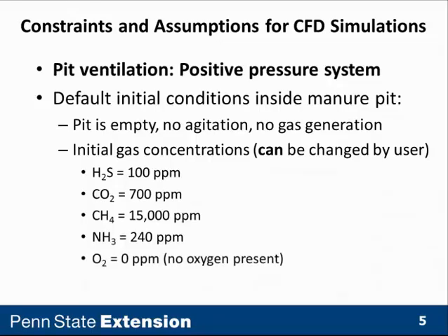The initial oxygen concentration inside the pit is assumed to be 0 parts per million, and this cannot be changed. So, let's suppose your oxygen content happens to be 10% by volume initially. Well, then the results of the gas replenishment simulation would be conservative, and it would certainly be satisfactory.